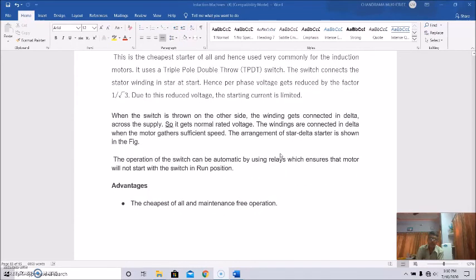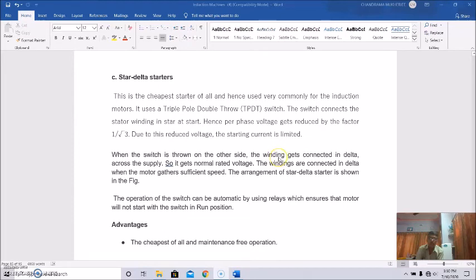Now, if we talk about the star delta starter. Actually, this is the cheapest starter of all, and hence used very commonly for induction motors. It uses a triple pole double throw switch. The switch connects the stator winding in star, and hence the phase voltage gets reduced by a factor of 1 by root 3. And due to this reduced voltage, the starting current is limited. But when the switch is thrown on the other side, the winding gets connected in delta across the supply, so it gets normal rated voltage, and the windings are connected in delta when the motor gathers sufficient speed.